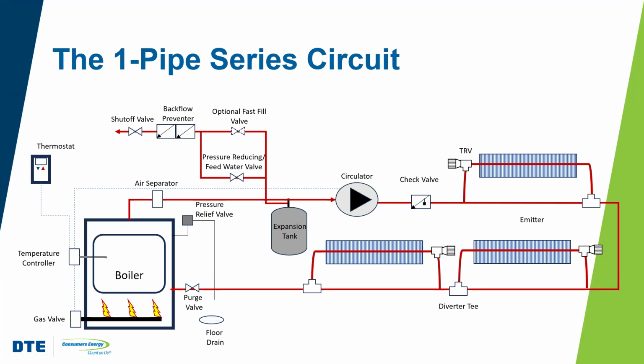And so you want to make sure that when you have a system like this, and this is fairly common for residential systems, you want to make sure that the emitters have been properly sized for their location in the system and the water temperatures that they're actually going to be seeing, right? And a system like this is good for systems that use fin tube or panel radiators, or if they use fan coil convectors, it's pretty good.